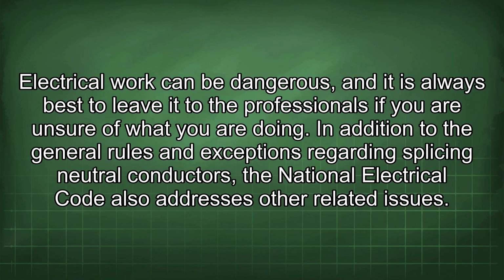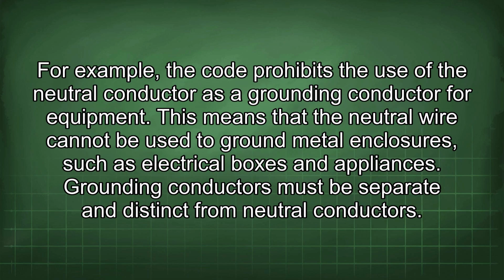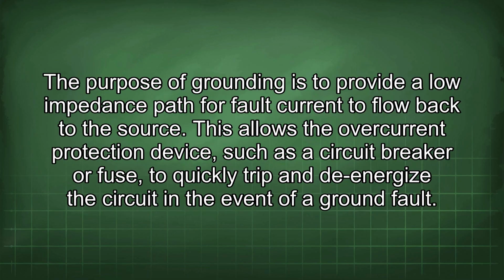In addition to the general rules and exceptions regarding splicing neutral conductors, the National Electrical Code also addresses other related issues. For example, the code prohibits the use of the neutral conductor as a grounding conductor for equipment. This means that the neutral wire cannot be used to ground metal enclosures, such as electrical boxes and appliances. Grounding conductors must be separate and distinct from neutral conductors. The purpose of grounding is to provide a low impedance path for fault current to flow back to the source. This allows the overcurrent protection device, such as a circuit breaker or fuse, to quickly trip and de-energize the circuit in the event of a ground fault.